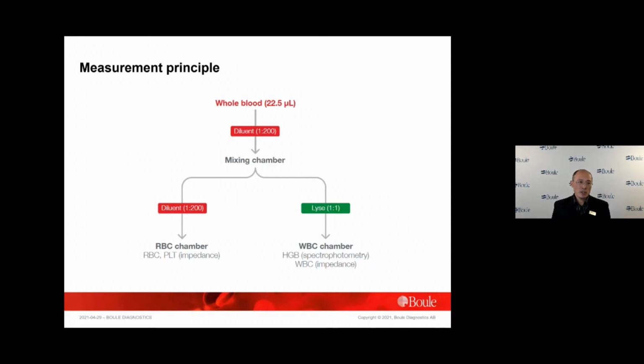The second dilution is separate. The diluted blood is again measured for a precise volume and then diluted one more time, 1 to 200, into the RBC chamber for measuring RBC and platelet. So from the whole blood, the final dilution for the RBC and platelet is 1 to 40,000. So this is a very high dilution ratio.